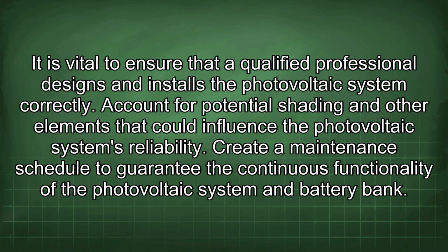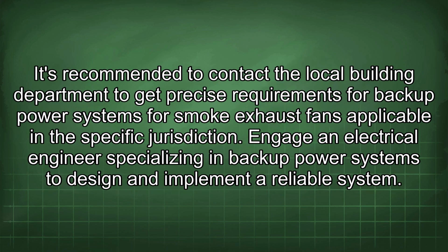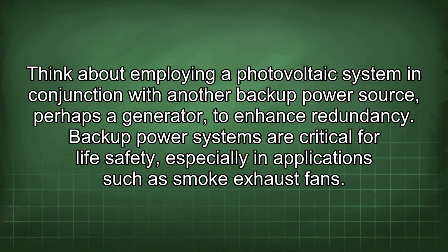It is vital to ensure that a qualified professional designs and installs the photovoltaic system correctly. Account for potential shading and other elements that could influence a photovoltaic system's reliability. Create a maintenance schedule to guarantee the continuous functionality of the photovoltaic system and battery bank. It's recommended to contact the local building department to get precise requirements for backup power systems for smoke exhaust fans applicable in the specific jurisdiction. Engage an electrical engineer specializing in backup power systems to design and implement a reliable system. Think about employing a photovoltaic system in conjunction with another backup power source, perhaps a generator, to enhance redundancy.